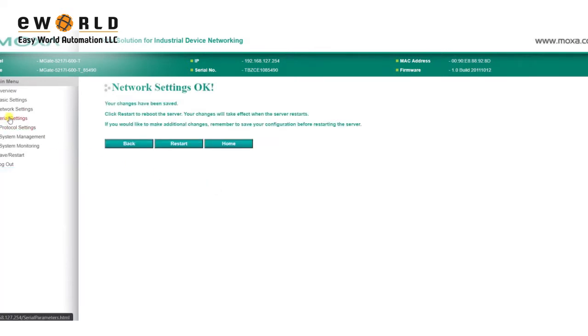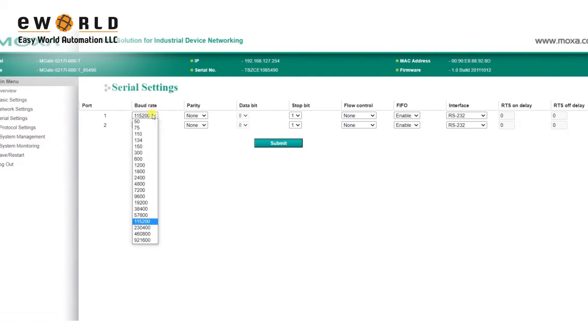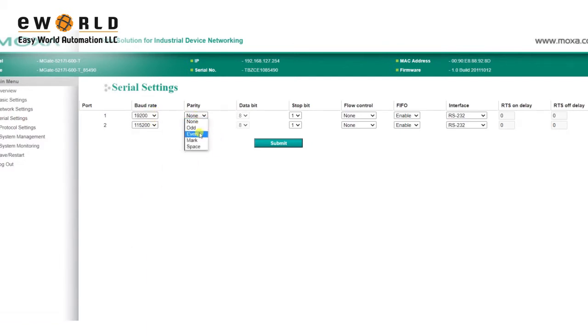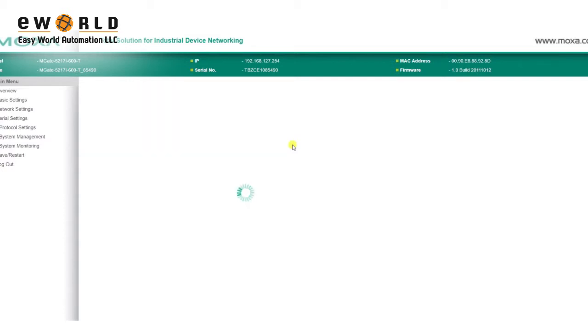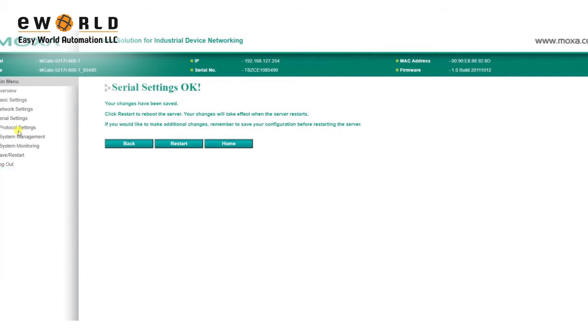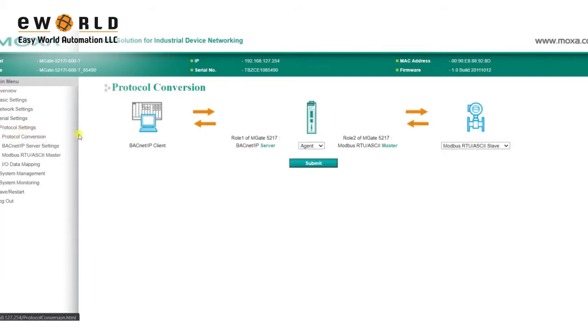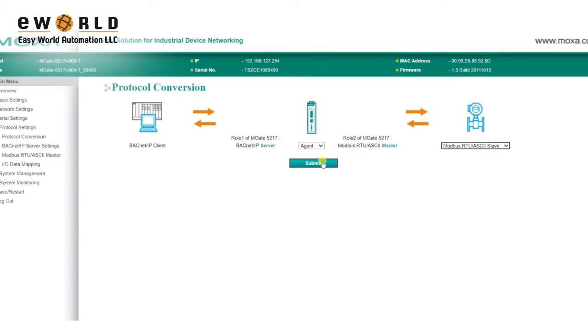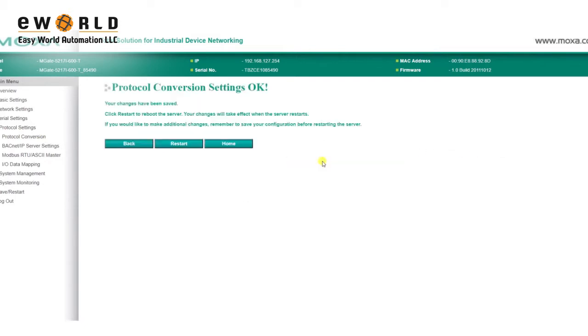On the Serial Settings page, enter the Serial Parameter Settings for your Modbus Slave device, such as the baud rate, parity, and which interface to use, then click Submit. Select your protocol by going to Protocol Settings, then Protocol Conversion. We'll select Modbus RTU ASCII Slave as our device protocol for our power meter, then we'll click Submit.